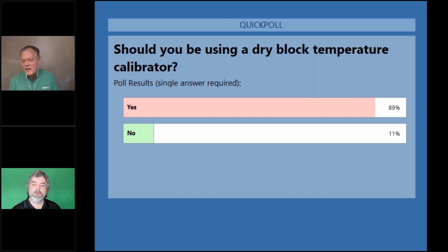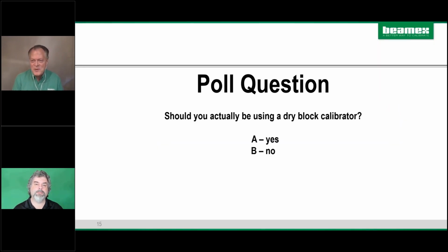At least we got you thinking about it, and pulling the sensor out of the process isn't scary - it's just something you maybe have to start doing. You don't have to do it every cycle. It's maybe a once a year check, or you'll kind of know when your probes - if your process has some questionable data, you might want to run out there and check it.